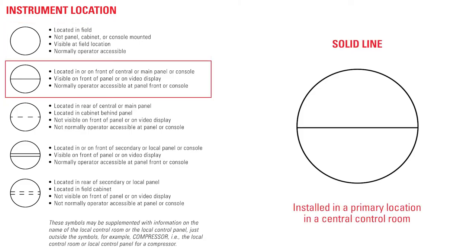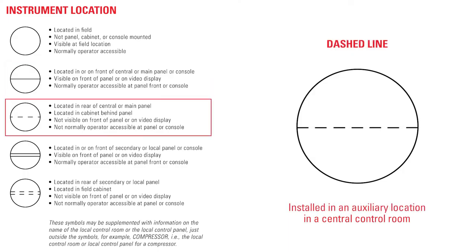A solid line means the instrument is in a primary location in a central control room, accessible to the operator. A dashed line tells us that the instrument is in an auxiliary location in a central control room, not accessible to the operator.